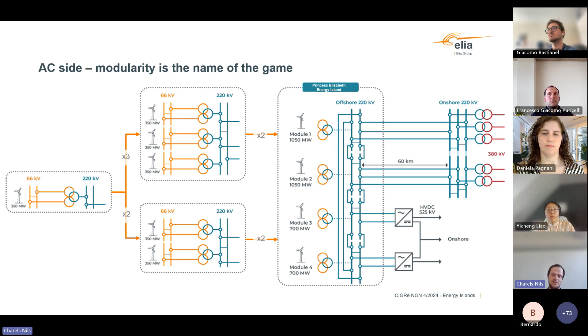So if you would have a failure on one cable or on one HVDC pole, via these links to the other modules on the island, we can still evacuate part of the power and maximize the use of the capacity that is available, especially considering that offshore wind does not have a capacity factor of 100%. So most of the time, there is spare capacity available on these parallel assets that you can use. So that is the AC side single line.